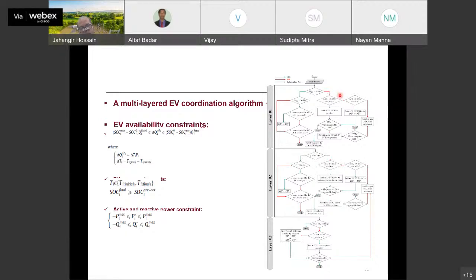This diagram shows the overall control for the microgrid. We have three layers of control. The first layer controls the DC bus - it checks whether it's maintaining the DC voltage requirement, considering the minimum and maximum values, and if it does not satisfy that range, it checks whether all the DC EV charging systems have any additional power we can utilize to regulate the DC voltage.